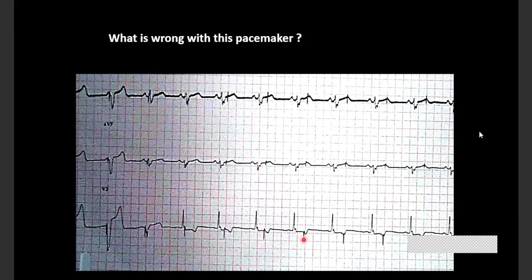This is really dangerous, because if this output falls on the T wave, it can result in an R on T. This looks like this patient has been programmed to an asynchronous mode. In an asynchronous mode, the pacemaker is completely blinded to sensing. It just keeps on pacing, irrespective of the sensing function. Sometimes we program the pacemaker to an asynchronous mode, like when the patient is undergoing a surgery, because cautery can interfere with the pacemaker. We want to shut off its sensing function. So in such cases, we switch off the sensing and just put it in an asynchronous mode. In an asynchronous mode, the pacemaker just keeps on pacing without any sensing.